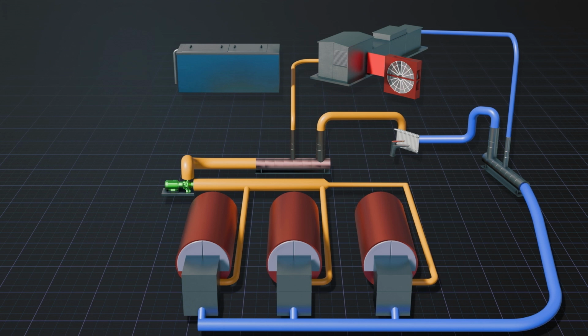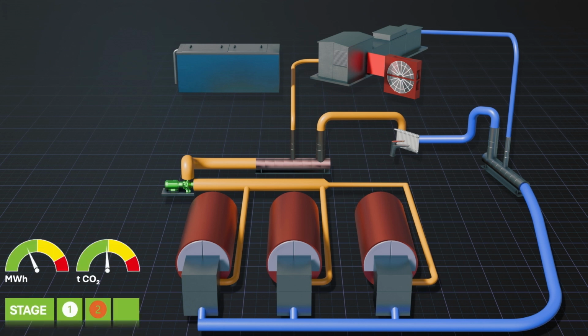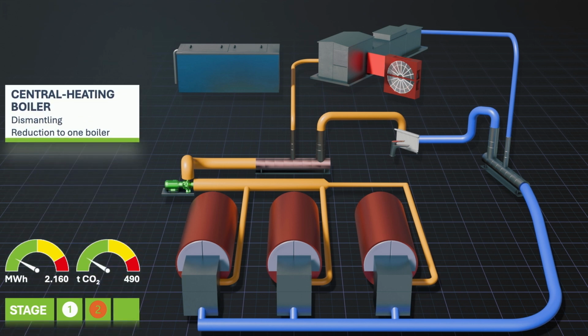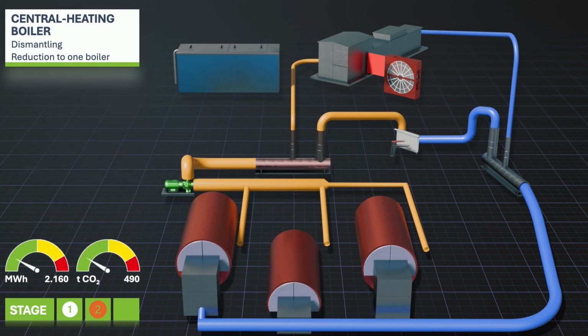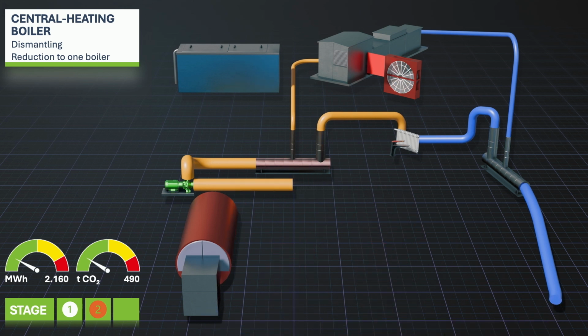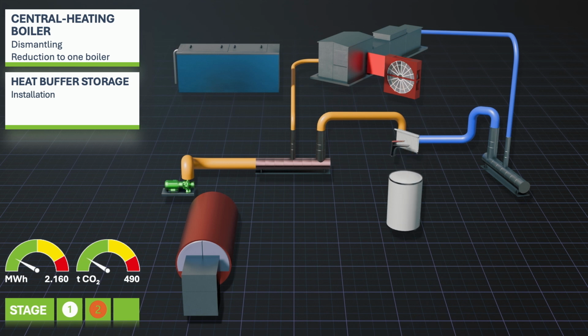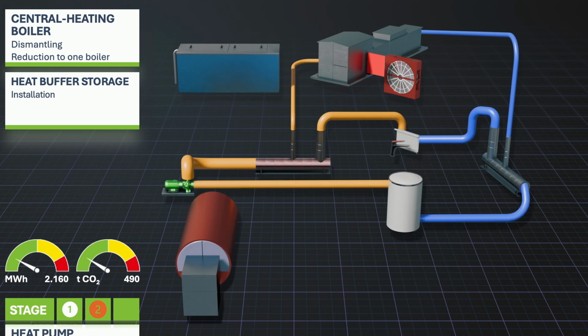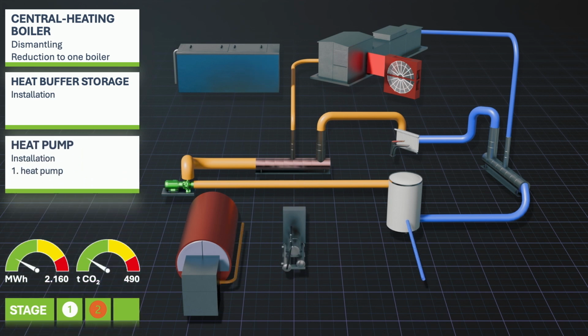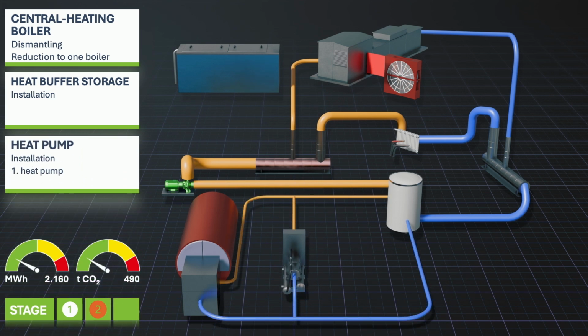Following the successful conversion of the distribution system, the heat generators can then be replaced in the second construction phase. The hydraulic conversion makes it easy to integrate the heat pump into the existing system. 2 gas boilers will be dismantled first. The third gas boiler will take over the peak load and be replaced later in the third construction phase. The switch to the heat pumps results in a considerable reduction in gas consumption of approximately 85%. The amortization for the second construction phase is approximately 3 years.